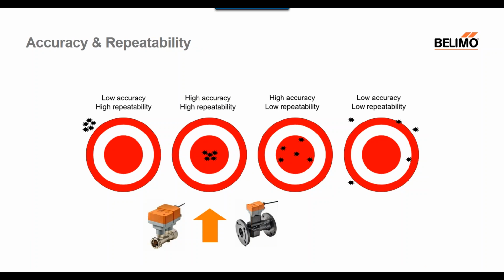Accuracy and repeatability. This slide really highlights the importance to have both high accuracy and the importance to have high repeatability. Repeatability is often ignored, but is an essential factor for long-term accuracy and performance of the flow sensors. When checking for specifications for flow sensors, it is important to verify repeatability to ensure system reliability in the long run.